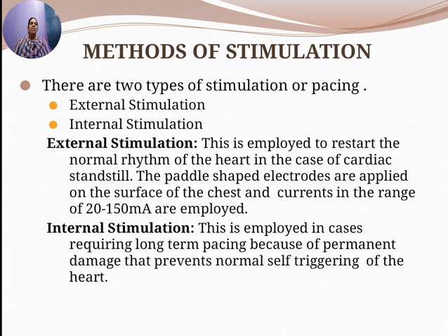Okay. So what is this artificial external stimulation or pacing? It is a method which is employed to restart the normal rhythm of the heart in the case of cardiac standstill. The cardiac standstill may be during an open heart surgery or whenever there is a sudden physical shock or accident. So the paddle shaped electrodes are applied on the surface of the chest, and currents in the range of 20 to 150 milliamperes are employed.